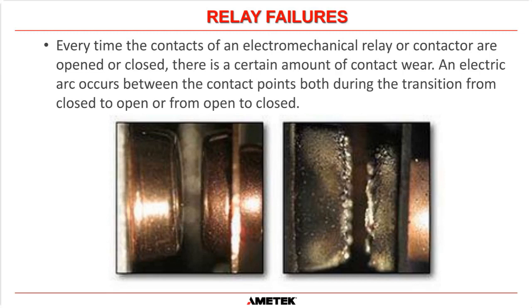Now, the next reason why we perform PMs is because of relay failures. Every time the contacts of an electromechanical relay or contactor are opened or closed, there's going to be a certain amount of contact wear, because whenever you open and close a contact, there is going to be some arcing. You can't prevent it. You're either making a circuit or you're breaking a circuit. And in doing that, there's going to be some arcing, and that will cause pitting of the contacts, basically. As you can see on the right-hand side here, this is the exact same picture of these contacts after they've been in operation for a long time. You can hardly see the copper, and you can definitely see the surfaces of these relay contacts are pitted now.